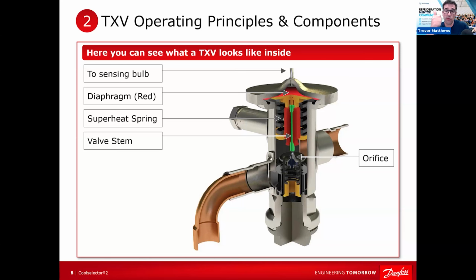All these valves come back, they're overheated a lot of times. I think the average max on most of them is around 250 Fahrenheit. It depends on what they have for it. If you look at the top of the valve, that diaphragm is what we call tool steel. Basically it is tempered steel. If you heat it up, you're going to take that temper out of it, and if you take that temper out of it, it is going to fail, usually where it connects to the sides of the power element. Because it cycles literally thousands of times an hour. It's pulsating, right? It's not just sitting constant. So over that life, if you take that temper out of it, it's going to fail, and you're looking at a dead TXV. So little things like this, you've got to be careful.